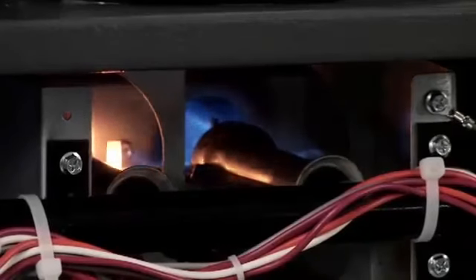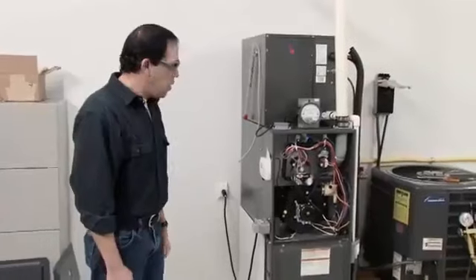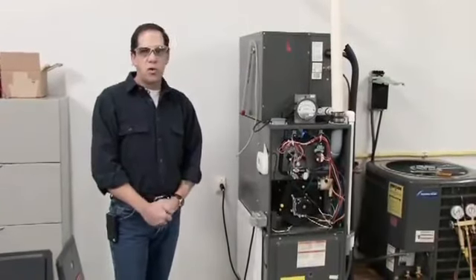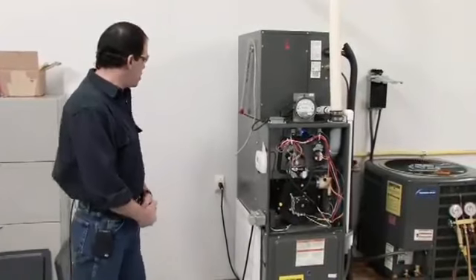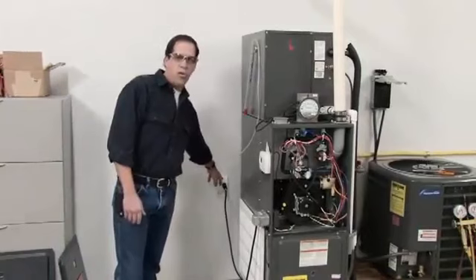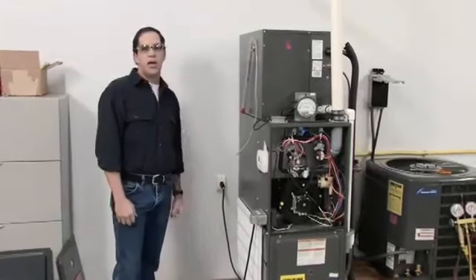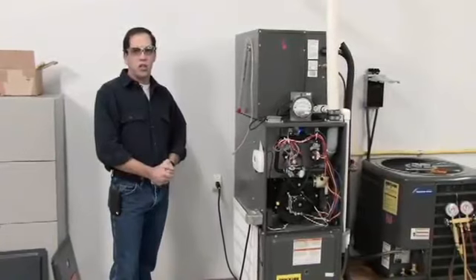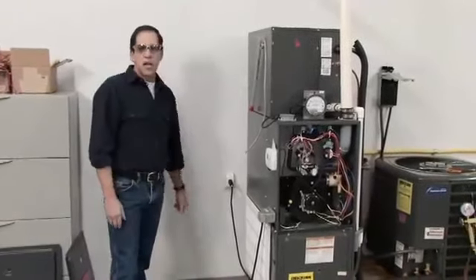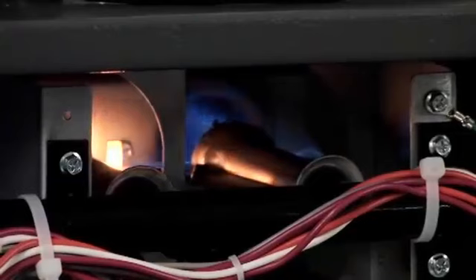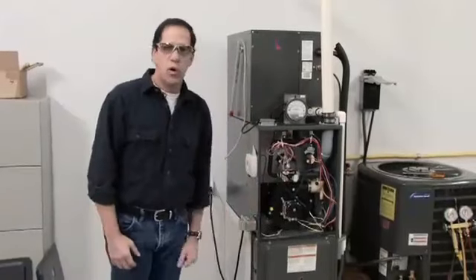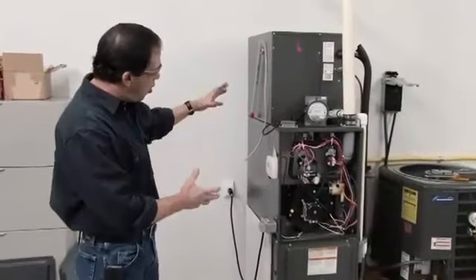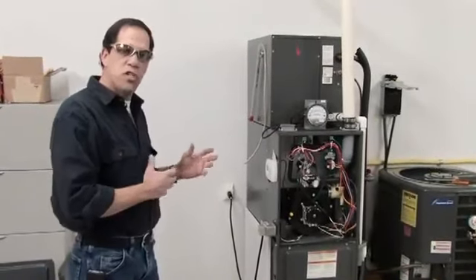Over here, we show that the furnace is under fire and we are burning. And what we're going to do is go ahead and set an alarm off on a smoke type detector or a CO detector. What you'll notice on the product is a flashing light. As the sensor goes off, we will see that actual LED start to flash in a little different sequence. As you notice, the alarm is going off, and you'll see that the LED is starting to blink more rapidly. And what happened in approximately 40 seconds, after the red light or LED has flashed rapidly, you'll notice that we have lost all of our power to our appliance. In the event of that detection, all of our equipment is now shut down, totally secure and safe.